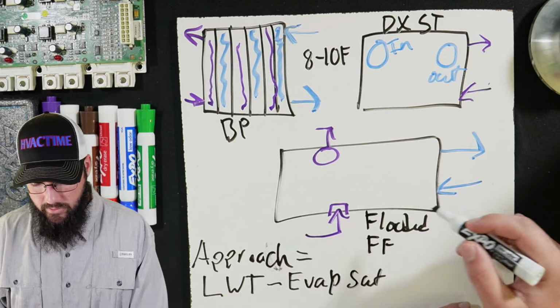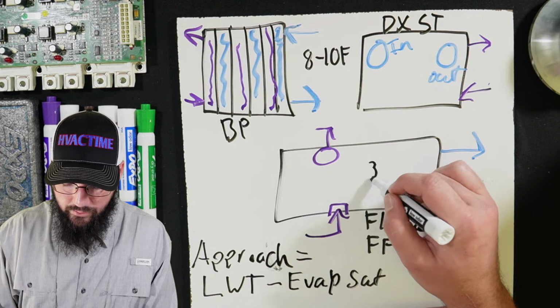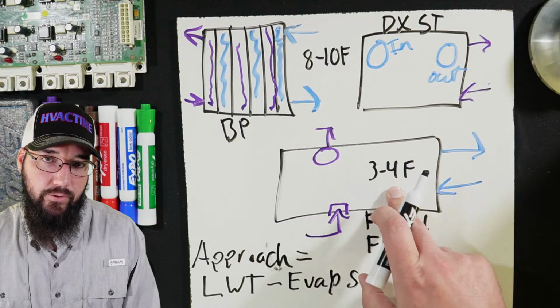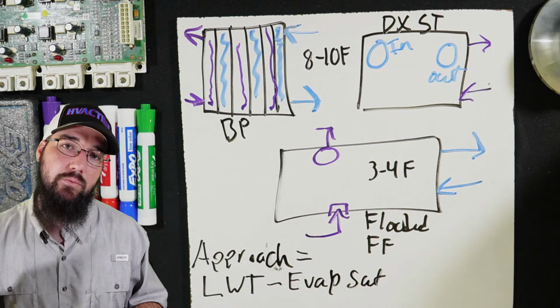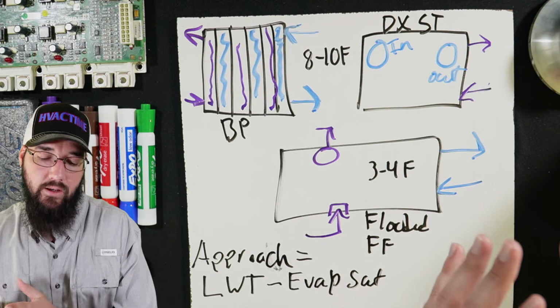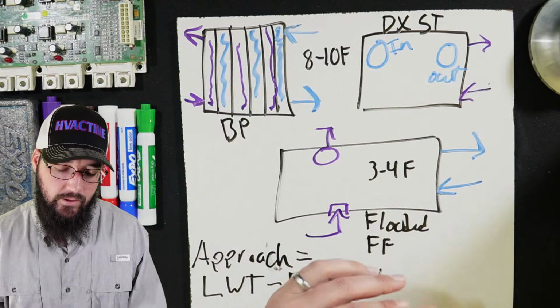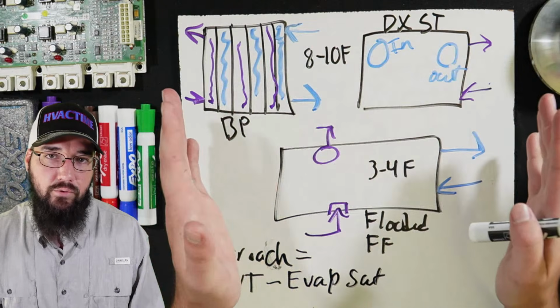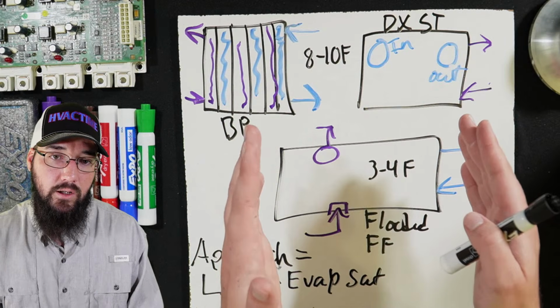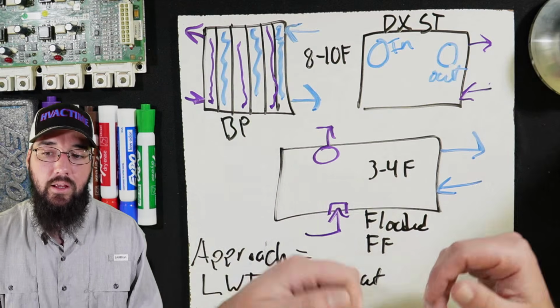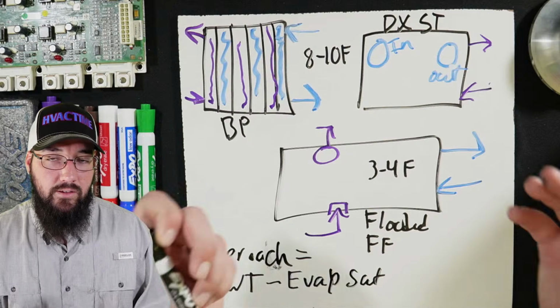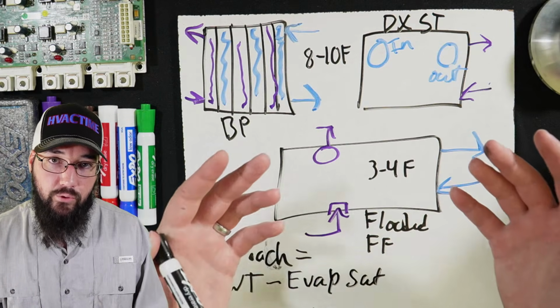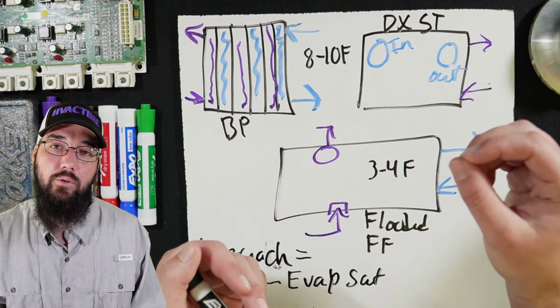This is at full load. Flooded and falling film are usually going to be running a 3 to 4 degree Fahrenheit approach at full load. I want to really hone in on that full load. What that means is as the machine unloads or derates itself, whether it turns compressors off, unloads them via slide valves, speed slows down, however that machine is doing it, you should expect this to drop. That would also mean that your differential across here, so if their design differential is 10 degrees from entering to leaving water temperature, so let's say we're going for 45 degree leaving, that's our target. We have 55 coming in. If it's designed for a 10 degree delta, that would be, with good GPM, a full load. I know there's a lot of technicalities here.